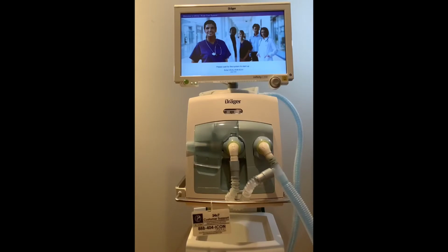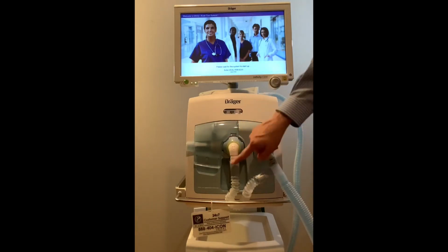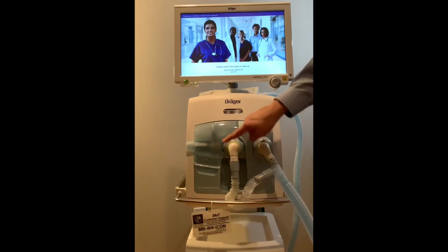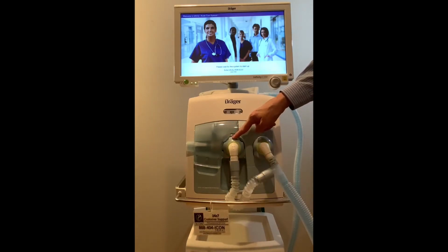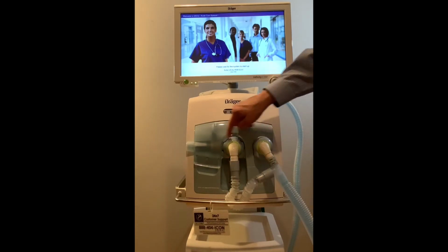To connect your circuit to the ventilator, the inspiratory limb of the circuit attaches to the inspiratory valve on the right-hand side of the ventilator box. The expiratory limb of the ventilator circuit connects to the expiratory valve on the left-hand side of the ventilator box.